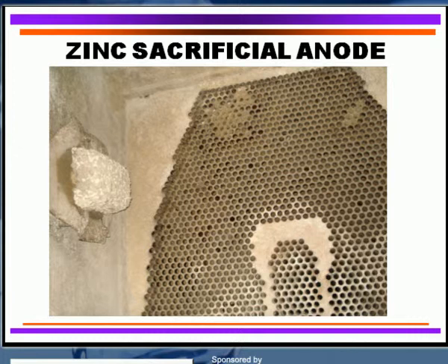Many people actually use magnesium, and the magnesium, of course, doesn't provide any inhibitor benefit to your equipment, but it is a very effective technique to use. Do not use aluminum. Aluminum is probably the worst thing you can use for sacrificial anodes because it produces a lot of aluminum deposits. It reacts with phosphate to cause severe depositing in the tubes themselves, so don't use aluminum. Use either zinc or magnesium.